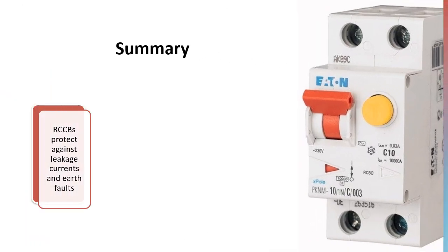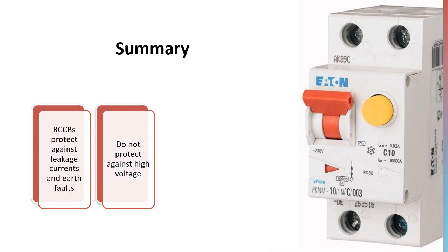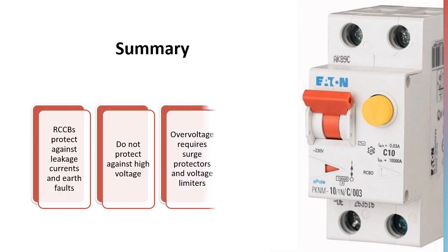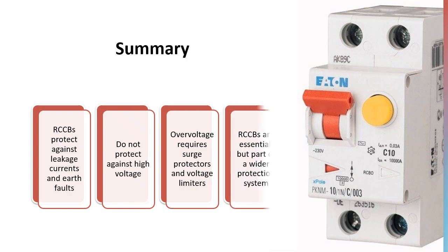Summary. To summarize, RCCBs are excellent at detecting and interrupting leakage currents and earth faults. But they do not provide protection against high voltage. Overvoltage requires separate protective devices such as surge protectors and voltage limiters. Therefore, RCCBs are an essential part of electrical safety, but they must be combined with other protective components for complete protection.